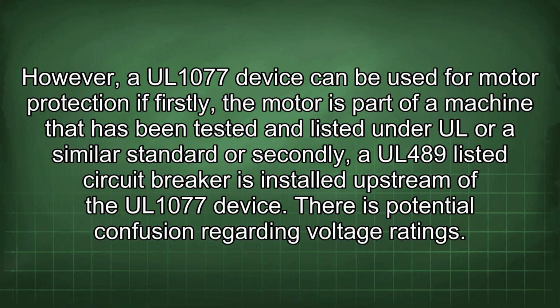However, a UL 1077 device can be used for motor protection if, firstly, the motor is part of a machine that has been tested and listed under UL or a similar standard, or secondly, a UL 489 listed circuit breaker is installed upstream of the UL 1077 device.